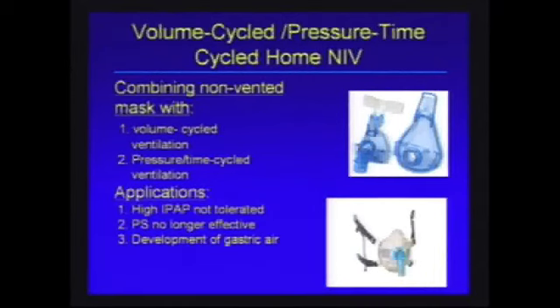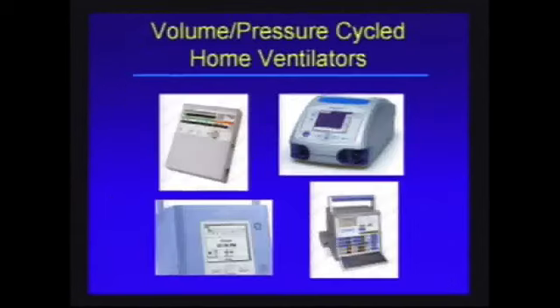So these masks are all identified by having some kind of off-color plastic shell. It's usually blue, and that indicates that it's not a vented mask, and that's a significant issue because you don't want to be using a non-vented mask on a BiPAP system or vice versa. You'll not get the benefit using volume cycle ventilators with a vented mask. Alternatively, some clinicians have actually taken vented masks and closed off the valves in order to use them, because the variety of masks for these volume cycle ventilators is pretty limited at this point. It's really something that's been used more in the acute care hospital arena. And now with the advent of these newer ventilators, this is something that's going to be used in the home care arena.